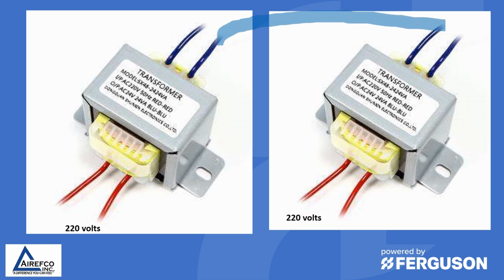So what we want to do is tie any of the two blue wires together, and then you want to take a voltmeter, or you can just touch these wires together, and if you get a spark or you get voltage, then you know that the transformers are not phased correctly together.